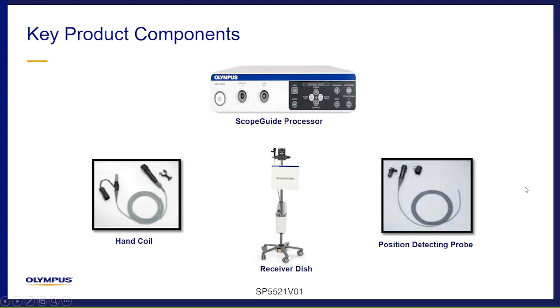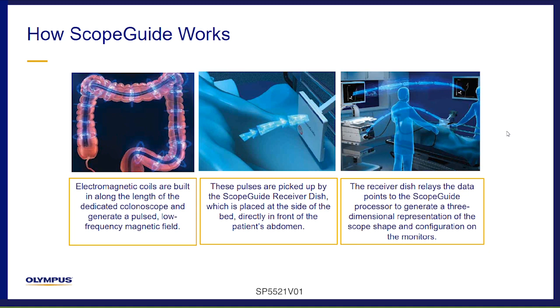Putting all that technology together, here you see on the left that the electromagnetic coils are built in along the length of the dedicated colonoscope, and they generate a pulsed low-frequency magnetic field. This is your receiver dish, which sits on the opposite side of the patient, right, across from the patient's belly. This receiver dish sits here and picks up the pulses from the scope. The receiver dish then relays that data to the ScopeGuide processor. The processor then sends it to the monitor, and then the monitor will show you the 3D real-time image of the colonoscope and its configuration.